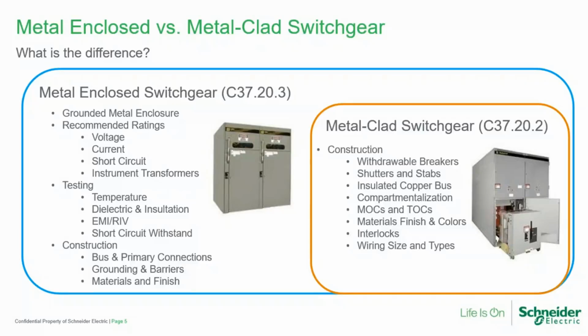So in one sense, it's very good. It was really written by the utility industry so that they could compare different manufacturers' metal-clad switchgear and get a very apples-to-apples comparison. The problem with the metal-clad switchgear standard is it doesn't leave a lot of room, or any room really, for innovation and change. There are some newer styles of metal-clad switchgear that have recently come onto the market in the past couple of years, and generally they involve trading ratings for footprint, and some different sizes of circuit breakers, but they still follow this general construction standard and are limited and barriered into this build standard.